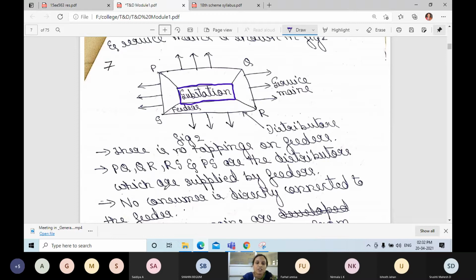These are the distributors which are supplied by feeders. Okay, from here to here, these lines are feeders. You can observe these lines. Okay, this one. Okay, these lines from substation to distributors, that line is called feeders. No consumer is directly connected to the feeders. Here PQ, QR, RS and PS are the distributors which are supplied by the feeders. You can observe, from substation to distributor it is connected by one line. Okay, that line is called a feeder.